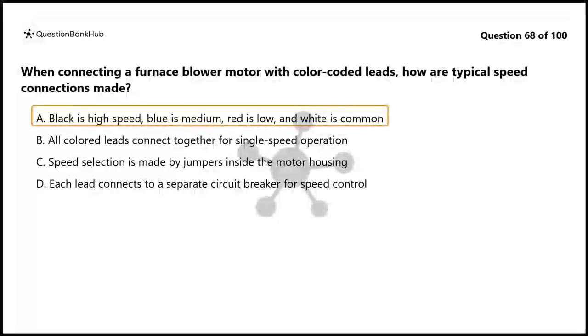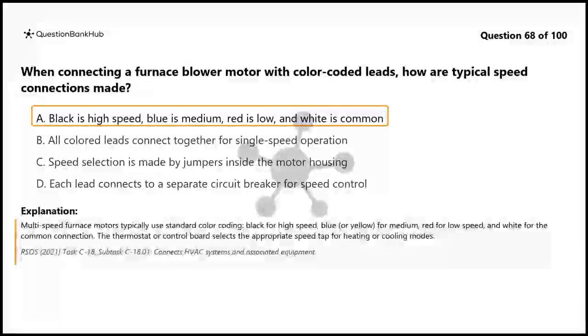The correct answer is A. Black is high speed, blue is medium, red is low, and white is common. Multi-speed furnace motors typically use standard color coding: black for high speed, blue or yellow for medium, red for low speed, and white for the common connection. The thermostat or control board selects the appropriate speed tap for heating or cooling modes.